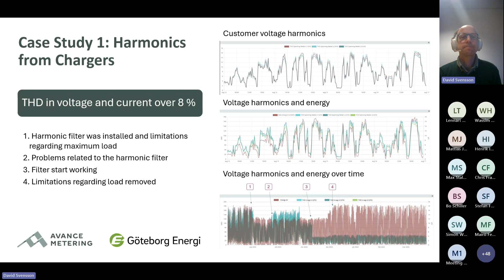In a huge grid area, our meters detected alarming events, total harmonic distortion levels exceeding the 8% threshold. While one customer appears to be the primary source at the medium voltage grid, other equipment under other substations is creating a harmonic hotspot. As you can see, it's spreading over a huge area, over lots of substations, but just a few of them are going over the 8% threshold. Some substations are below. And just like case one, the harmonic patterns are proving elusive, making it a true power quality puzzle to find out what's going on.